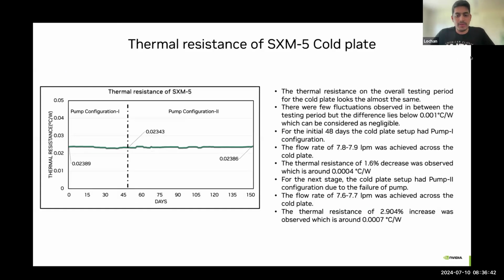So for this experiment, on the cold plate side, we were observing three main parameters. The first one was the thermal resistance of the cold plate. The second one is the pressure drop. And the third one is the flow rate of the coolant across the cold plate. For the 150 days of operation, initially we were looking into how much the thermal resistance varied from day one to day 150. On the initial day of testing, we were able to see 0.023 degrees C per watt of thermal resistance.